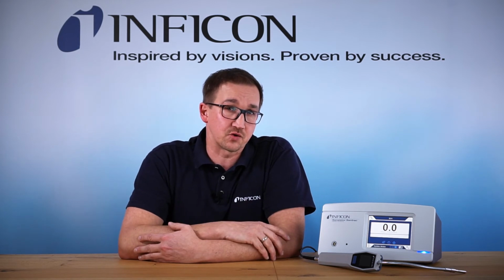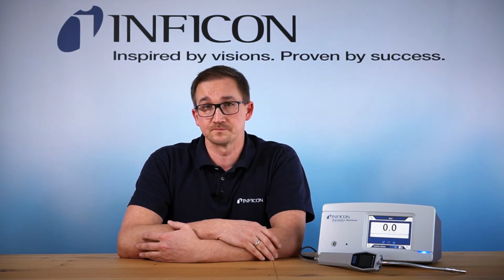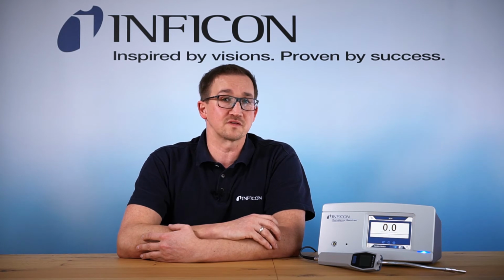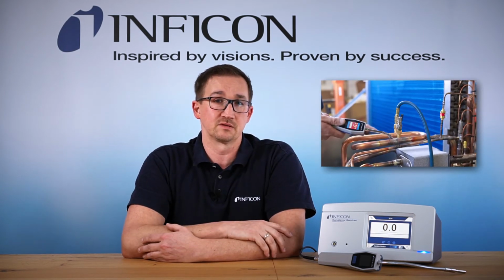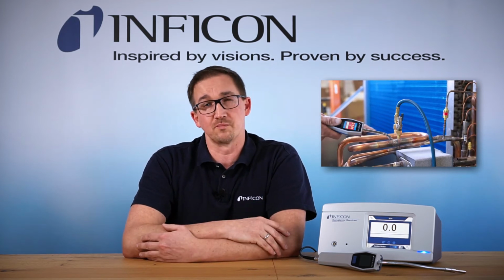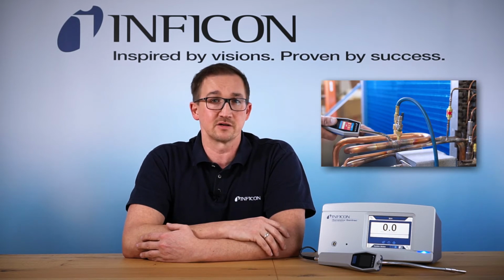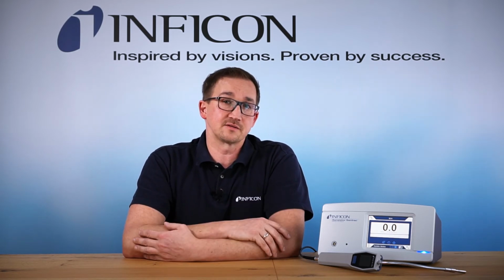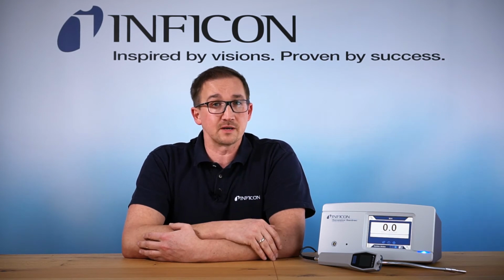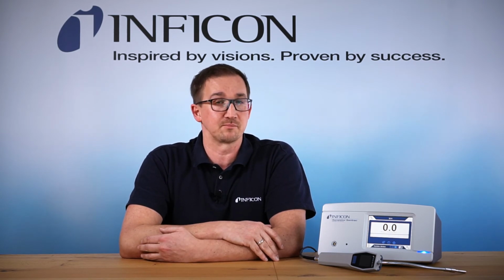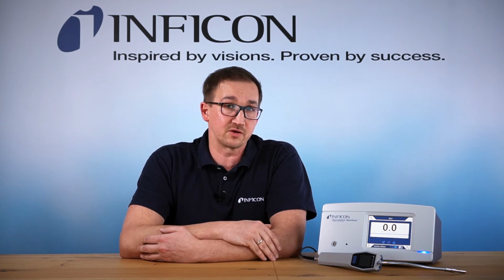Should you consider the new Sentrac Strix edition? The Strix sensor gives the most added benefit for finding small leaks, in the range of 10⁻⁵ millibar liter per second. Typical applications for these requirements can be found in the refrigeration and air conditioning industry, where in the pre-test of components and refrigerant cycles you need to find leaks corresponding to just very few grams of refrigerant loss per year. Quite similar to the automotive industry and pre-testing of mobile air conditioning units. The phenomenal sensitivity of the new Strix sensor, however, means that hydrogen can now be considered for testing fuel systems, which are typically specified in the 10⁻⁵ range as well. For many of these and similar applications, the new Strix edition is the ideal tool.